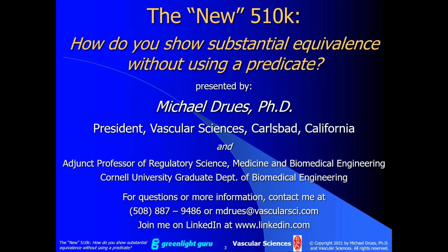If that's the case, then I'm sorry to burst your bubble, but you won't qualify to use the SP 510K program. You could flip to an abbreviated 510K because, as I said before, with the abbreviated 510K you have your entire universe of medical devices to choose from.